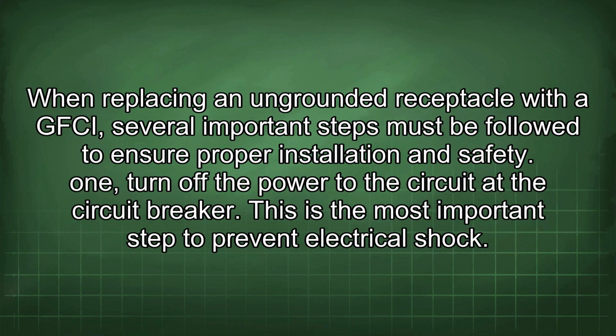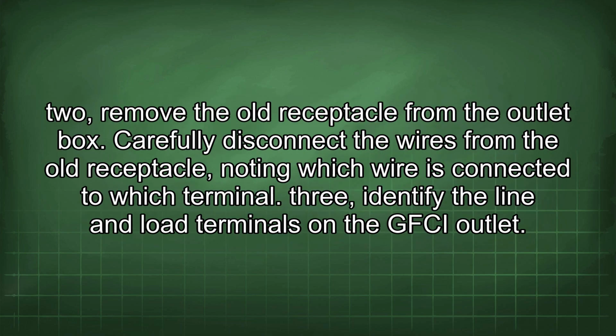When replacing an ungrounded receptacle with a GFCI, several important steps must be followed to ensure proper installation and safety. 1. Turn off the power to the circuits at the circuit breaker. This is the most important step to prevent electrical shock. 2. Remove the old receptacle from the outlet box. Carefully disconnect the wires from the old receptacle, noting which wire is connected to which terminal.